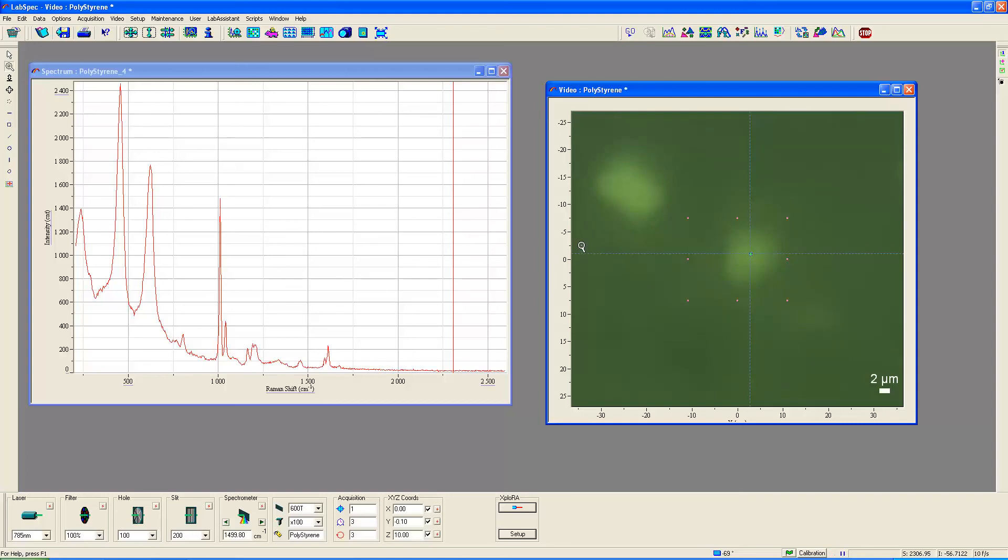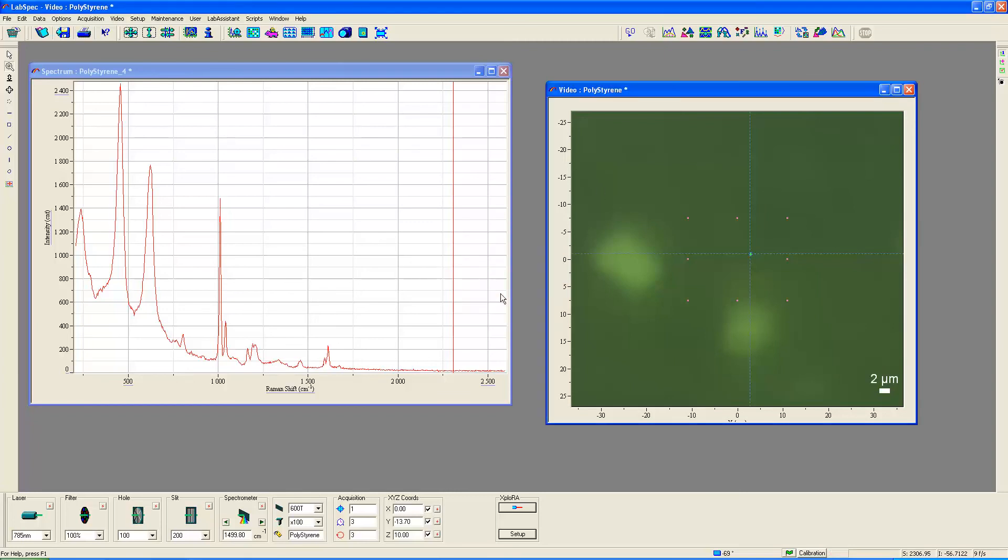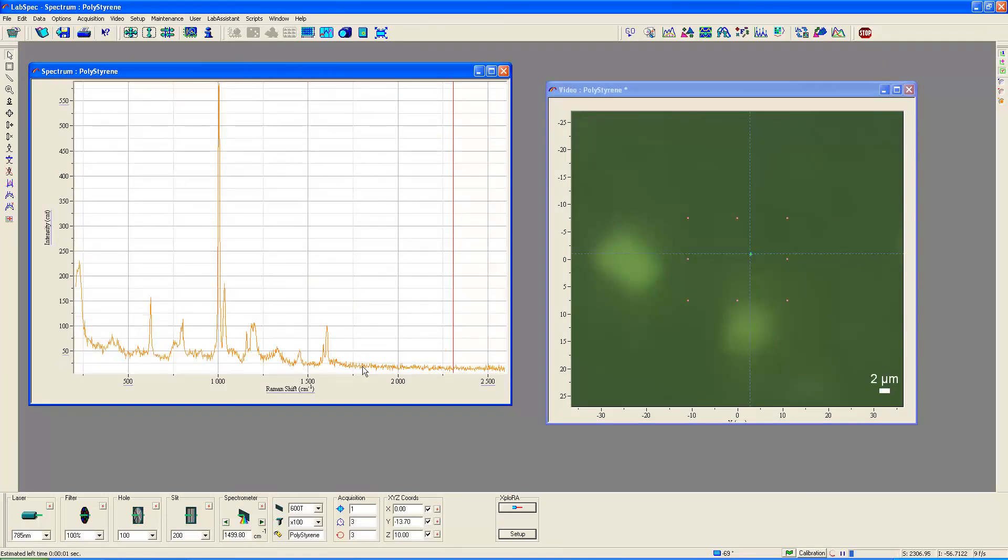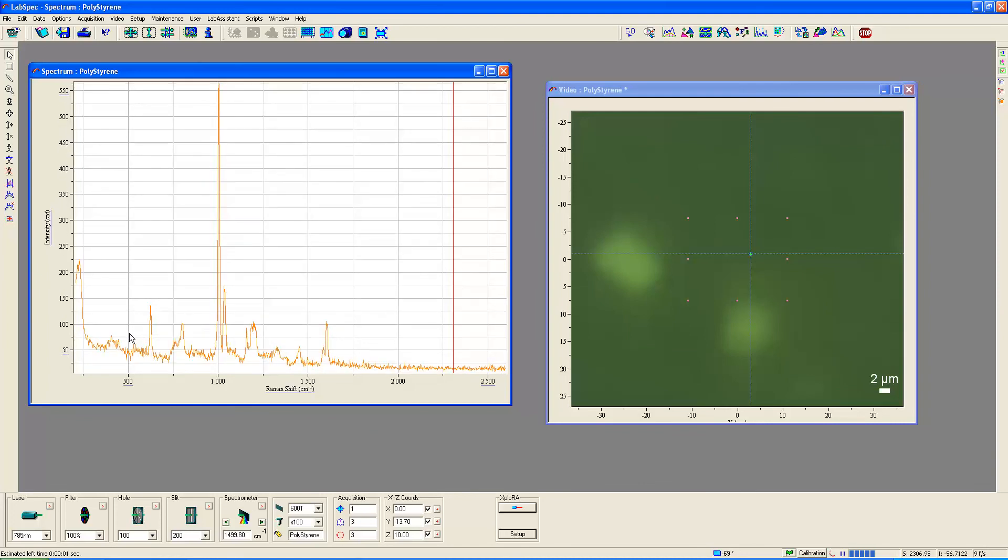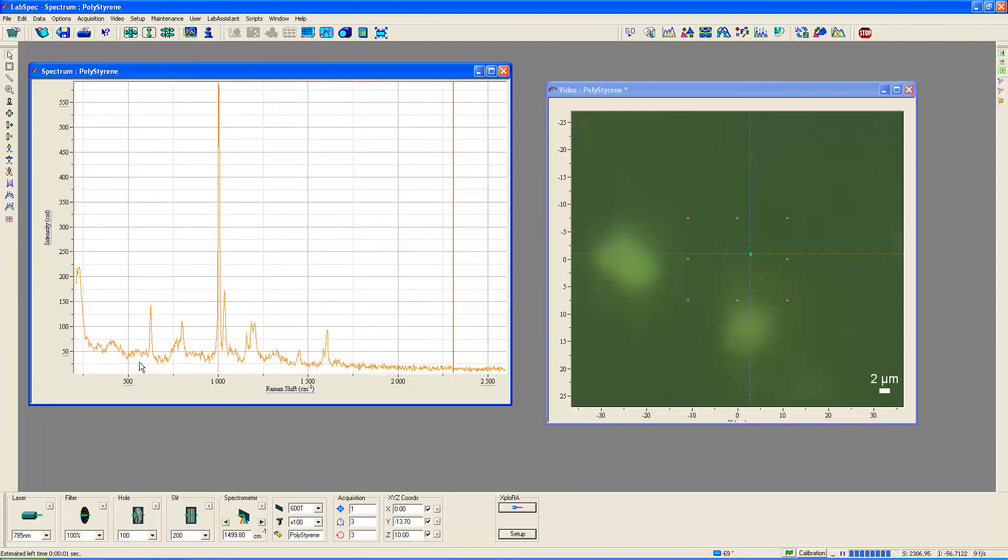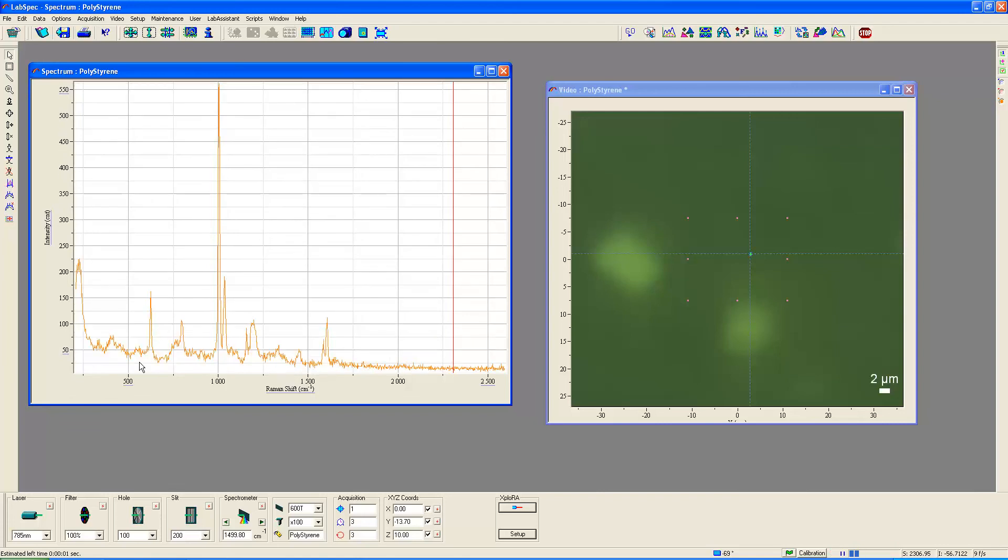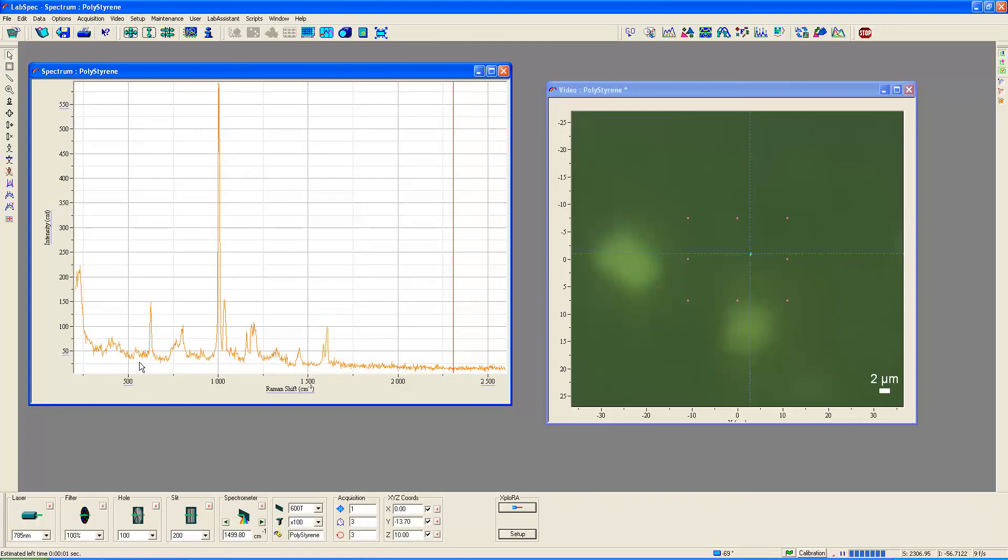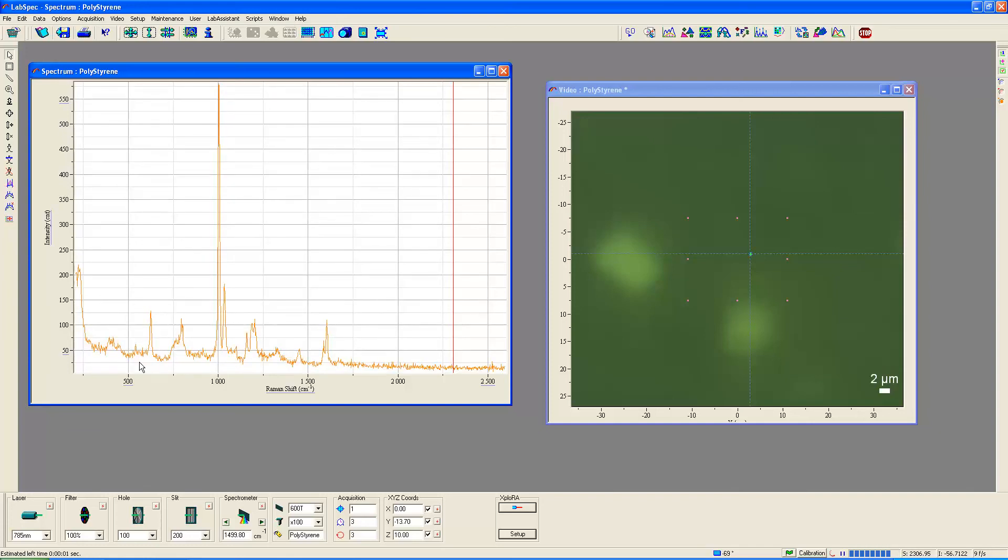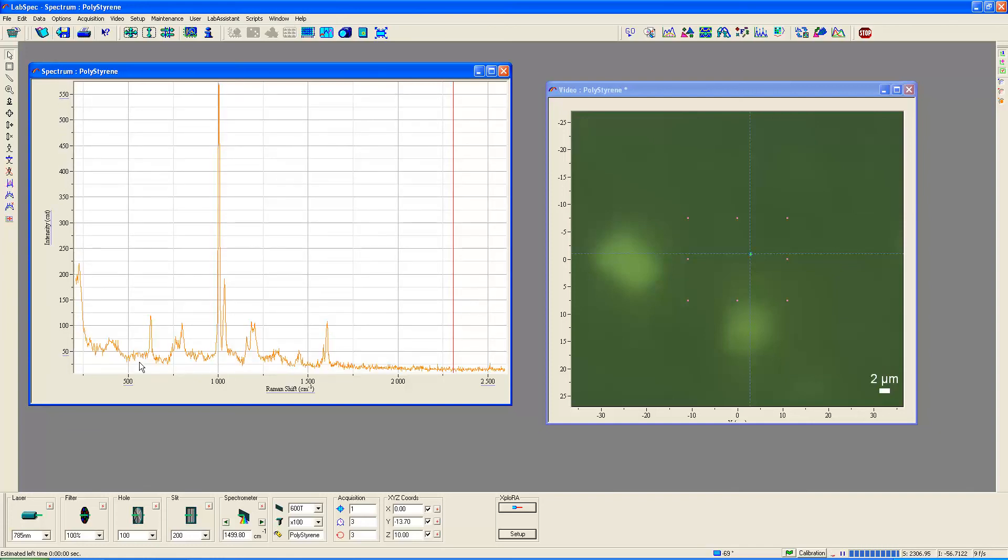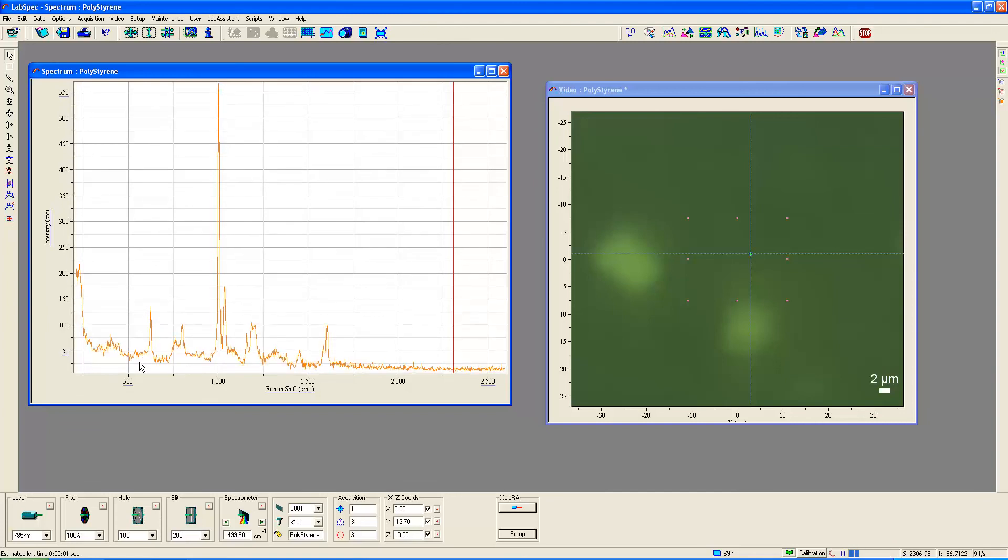And why don't I just, to illustrate this point a little further, why don't I just move off of, this is where the laser beam would be, right where this green spot is. I'm going to move off of that spot. Stop the video camera. Go back to position 1. And now let's go back to real-time display. And our laser is on. And lo and behold, there's no titanium dioxide. And that's because we've moved off. So we are able to, through the confocality of the Explorer instrument, we're able to resolve, spatially resolve, a chemically heterogeneous component within this polystyrene film.